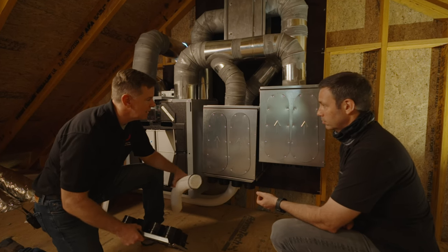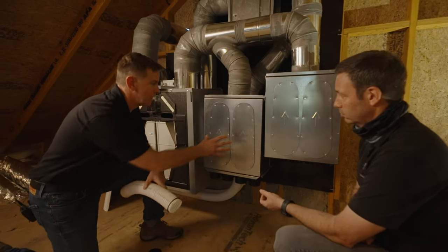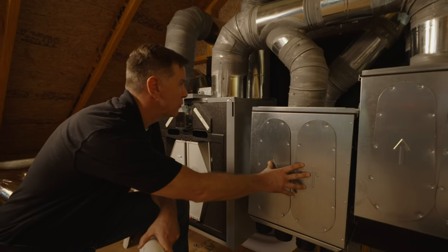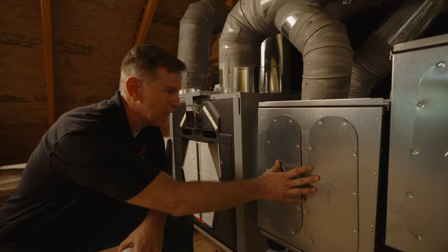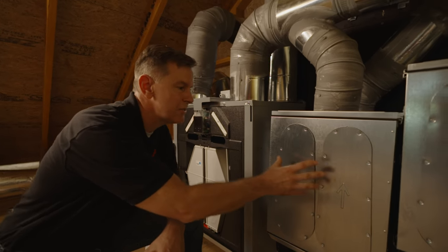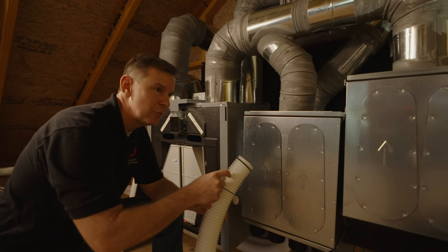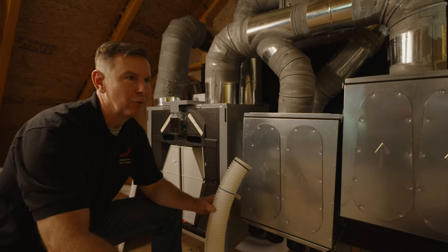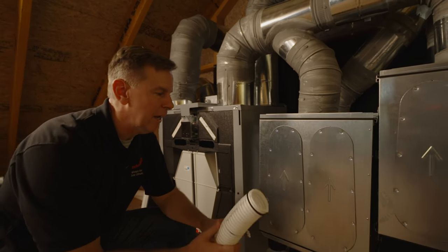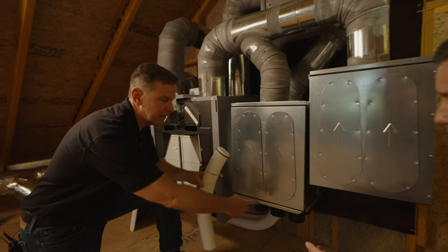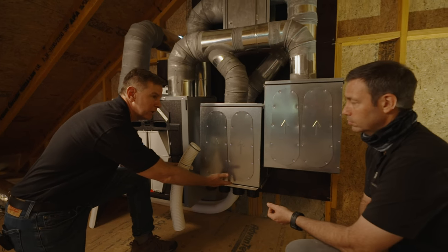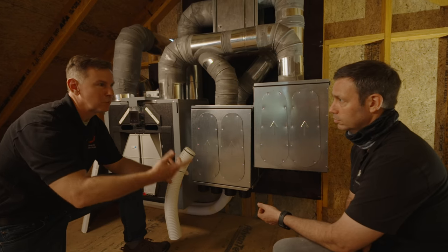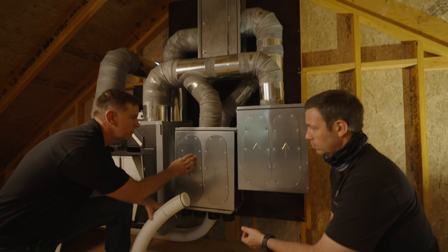This main part of the box is actually a silencer. In this case, it's the return side, so it's going to keep exhaust fan noise from going down these tubes to your bathroom or wherever. It also keeps crosstalk between rooms from happening, since we're connecting all the rooms to one manifold. So the silencer's good.